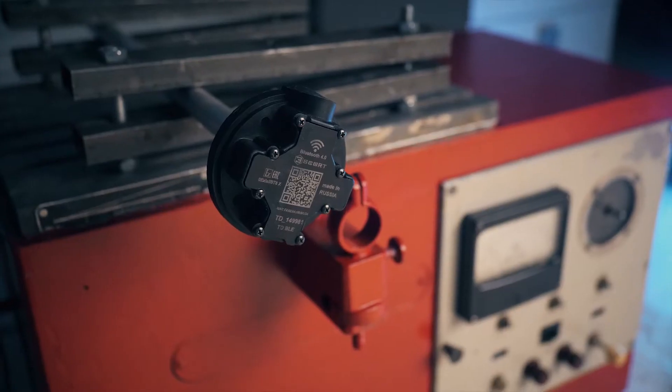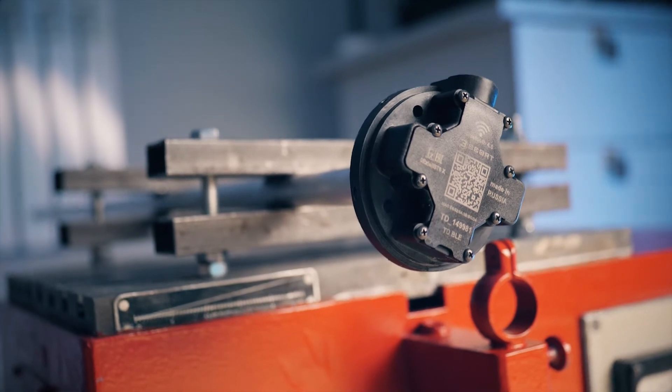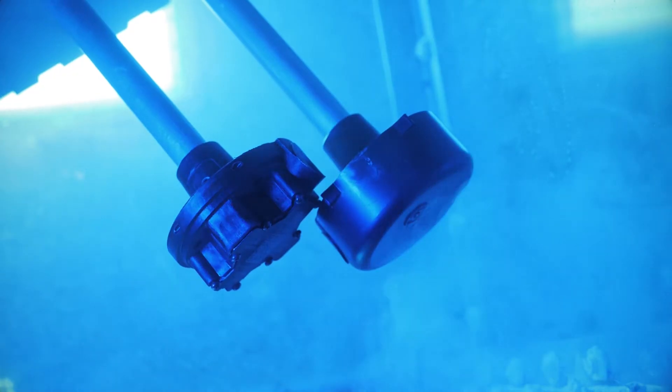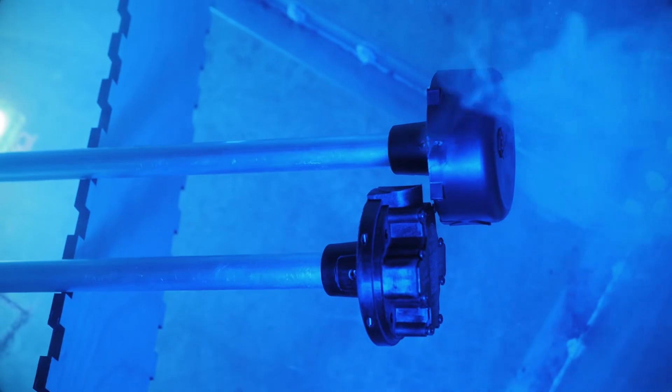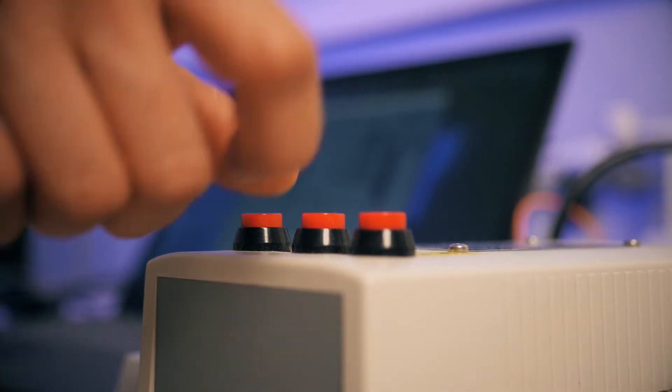The next stage of testing is a vibration stand. Then, at the testing stage in the salt chamber, we check the corrosion resistance of the products under the influence of a specially created salt mist, as well as resistance to a humid atmosphere with increased salt content during operation. The final stage is to check the linearity of the sensor, as well as the dead zone and smoothing on the actuator.